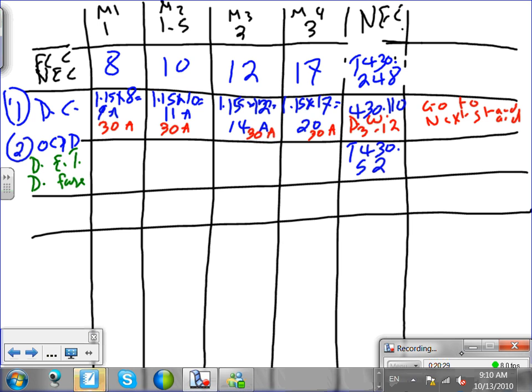1.75. Everybody can read this table, guys. There are columns and there are rows. You can go to single phase motors, induction motors, under dual element time delay fuse, cross-reference the column with the row. What do you get? 1.75. Mr. Erbab, cross-reference the dual element time delay fuse with single phase motors, induction motors, you get 1.75.